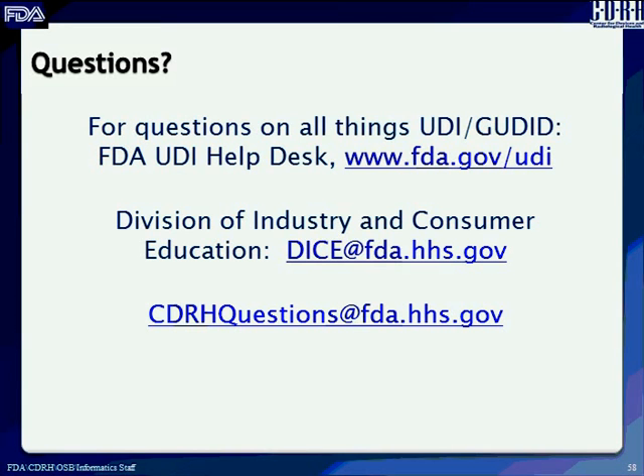No, this is just my question right now from the slide that you provided to us. In the human readable one of that barcode, we have the DI, and then the PI; the manufacture date is not part of the UDI human readable one. However, we have the manufacture date listed and stated on the label. So when we are entering the data in GUDID, should we say yes for manufacturing date or no?